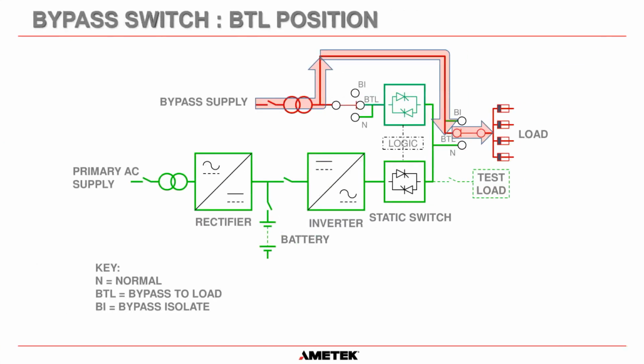The next position is bypass to load. And you can see the power flow now. On this contact, we have now moved to this position, so we are no longer going from normal to this point. Now the UPS is not feeding the load. Bypass is now going out here, along here, down through this bypass to load switch, out through the loads. But you can see that bypass still goes through the static switch. That's important because you have to have the static switch on bypass before you move the mechanical switch to bypass to load.